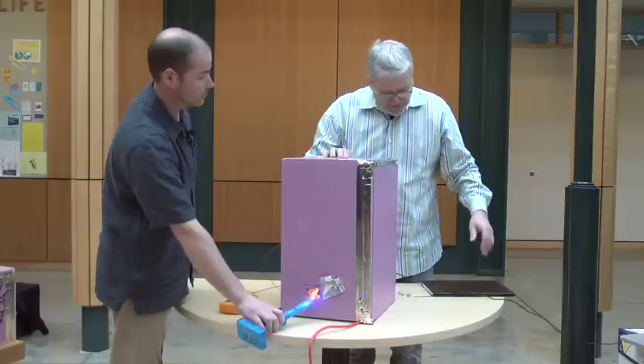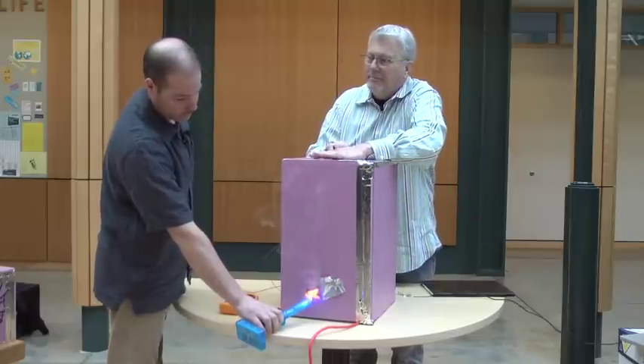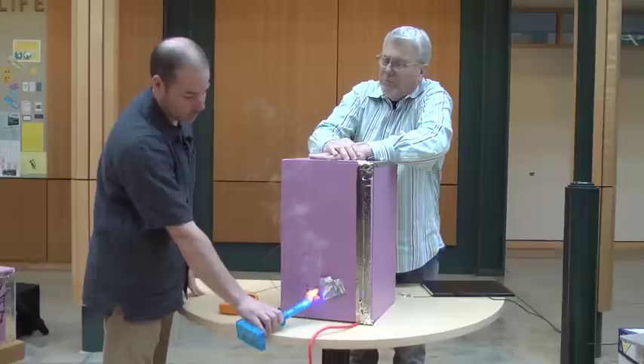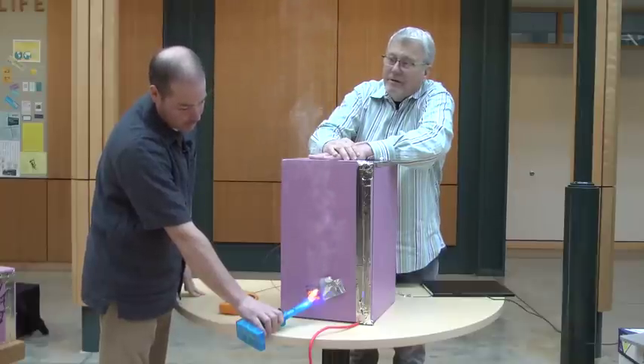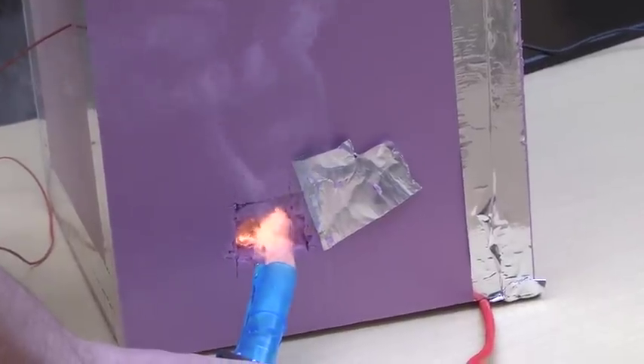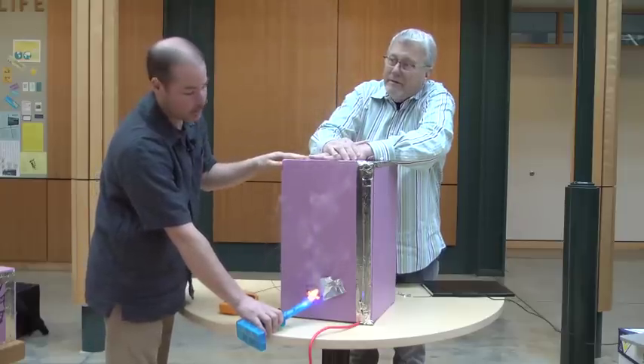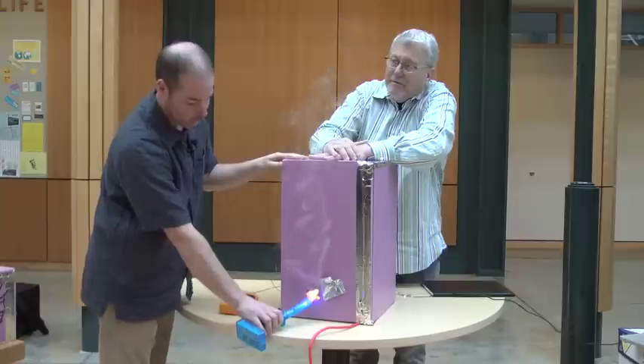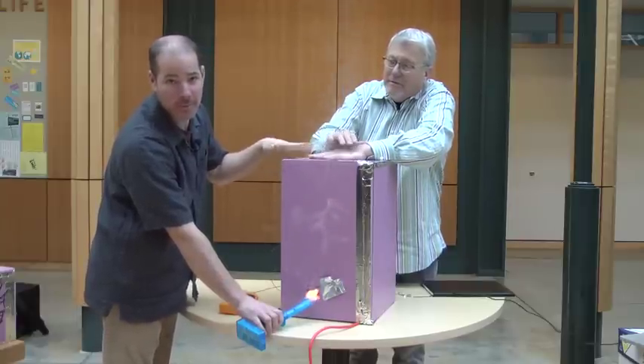And it would be interesting to see what happens if I close this hole up. All right. So Spencer has access to the hole in the attic and he seals it up. Now notice how much of the smoke is not actually even entering the building. Just by sealing one of the major air leaks at the top of the building. And this is demonstrating why when we instruct people to do air sealing, we tell them to focus at the higher part of the building first. It's the best bang for the buck.